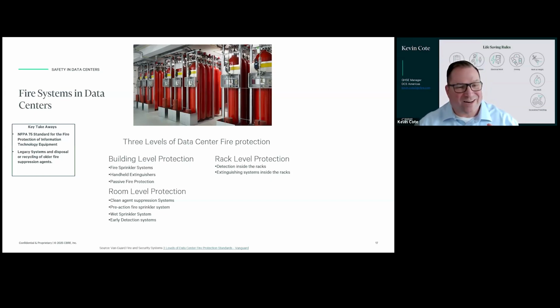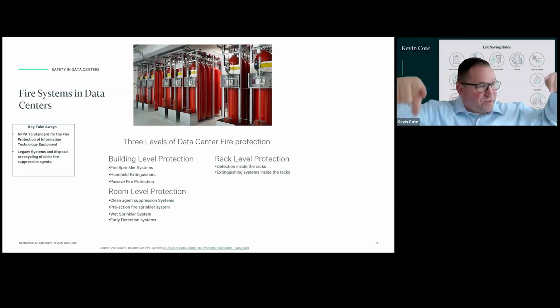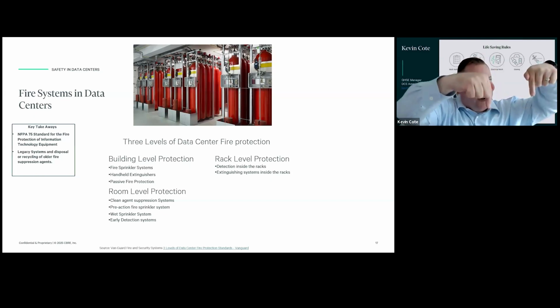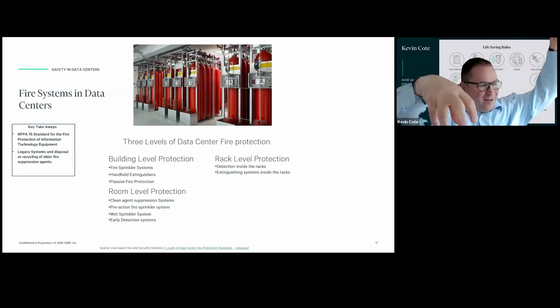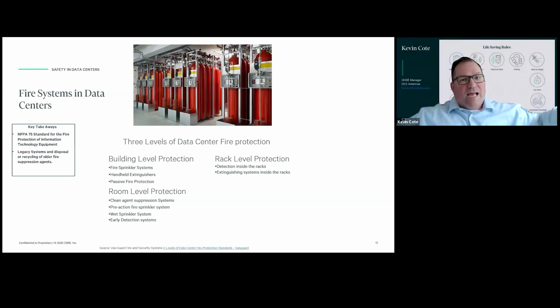As we were just talking about, dust can set it off, but usually that's an active system where there's a pump. In certain areas, usually down the aisle, you'll see little hoses dropping down within the aisles. From that, there is suction, and that air is brought into the system and then into detection. Generally it's looking for particles, really smoke particles, but dust can trip it off. That would be your early detection system. All these areas are monitored by what is called a BMS, a building management system, so you'll see at the control room that there's something going on that needs to be looked at.